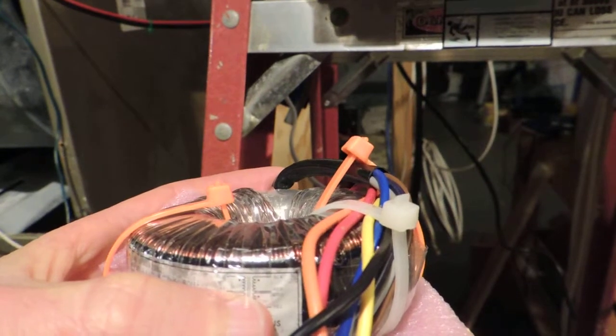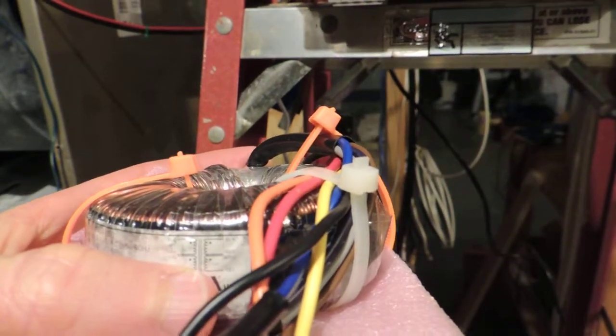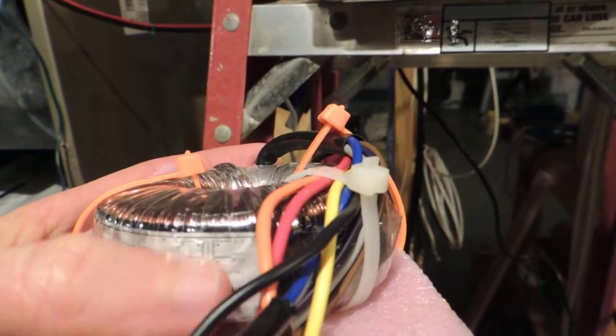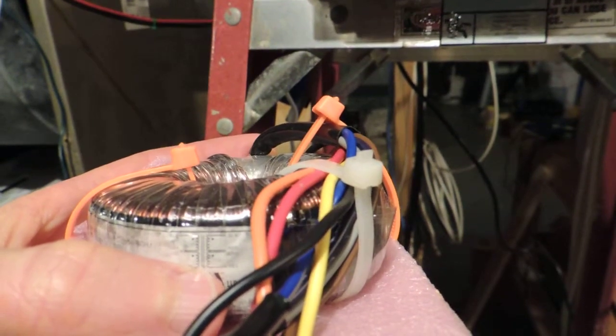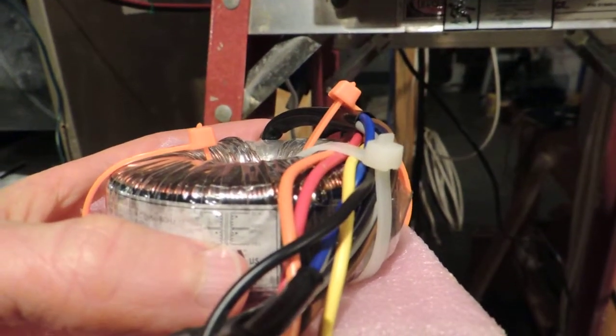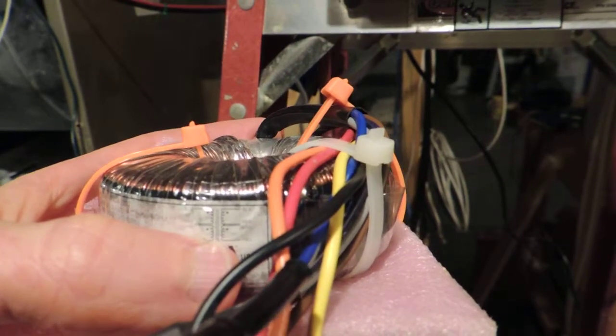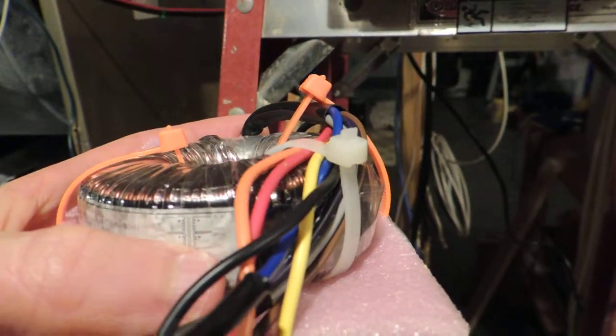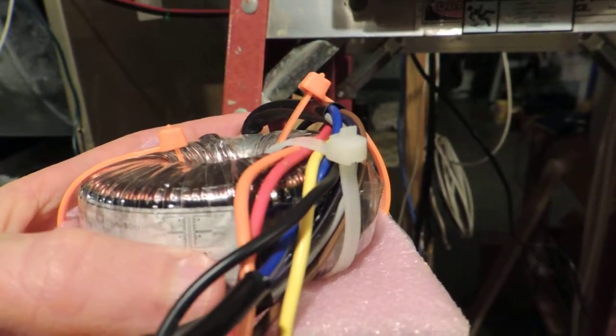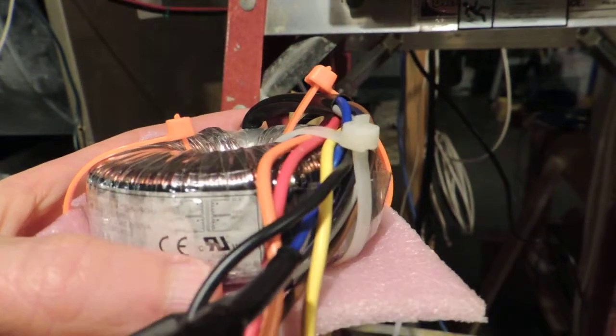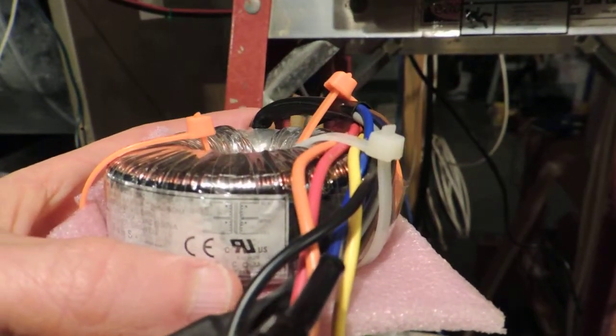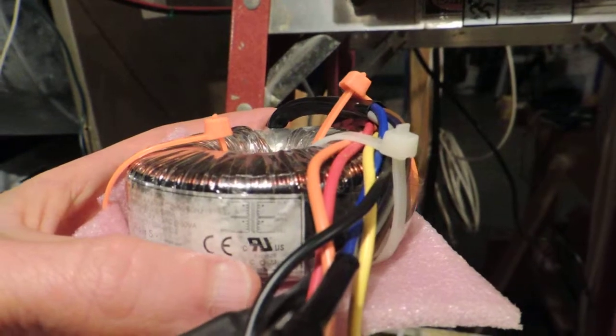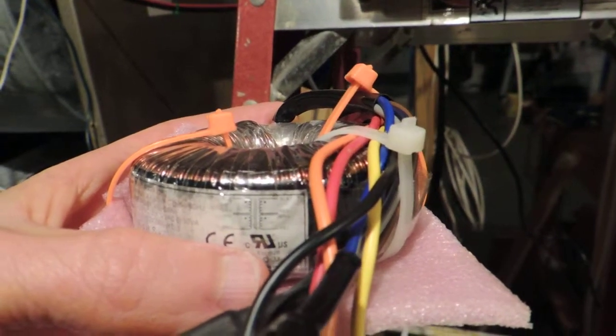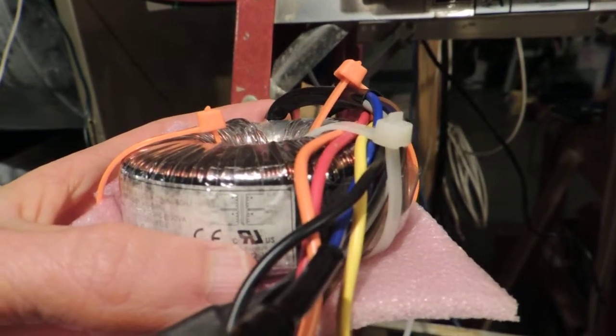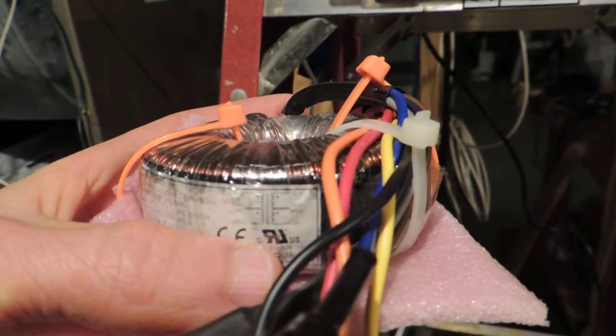The output phase to phase, across the full secondary seriesed up, goes to the thermostat. Then I took half of a phase here, or just one leg — in other words 12 volts instead of 24 volts — and ran that over to both my alarm system, which uses an AC supply, and the doorbell as well.